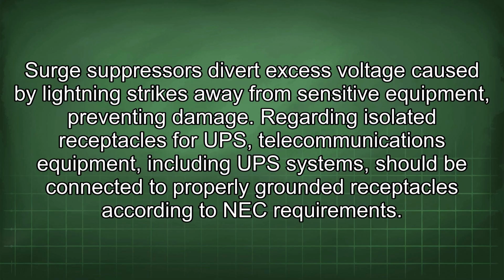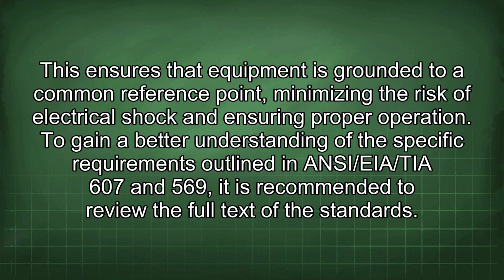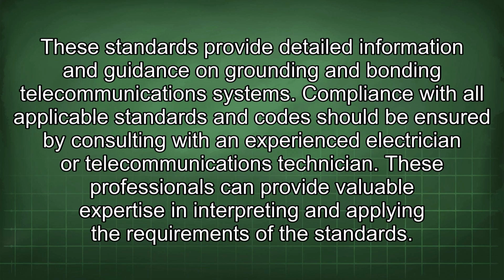Regarding isolated receptacles for UPS, telecommunications equipment, including UPS systems, should be connected to properly grounded receptacles according to NEC requirements. This ensures that equipment is grounded to a common reference point, minimizing the risk of electrical shock and ensuring proper operation. To gain a better understanding of the specific requirements outlined in ANSI/EIA/TIA 607 and 569, it is recommended to review the full text of the standards. These standards provide detailed information and guidance on grounding and bonding telecommunications systems.